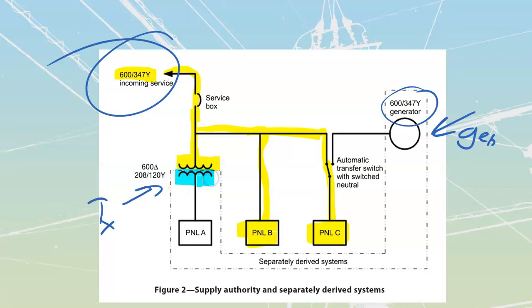This is going to be a separately derived system, and I see that this separately derived system over to panel A has no connection over to the rest of it, so it's going to need to have its own grounding set up because it's a 208/120Y. And if I've got an automatic transfer switch that has a switched neutral inside of it, this is also going to need to have a separately grounded type of system that we're going to create.